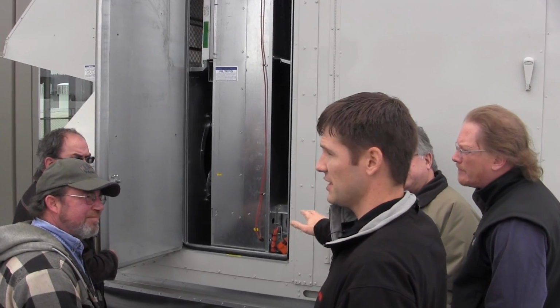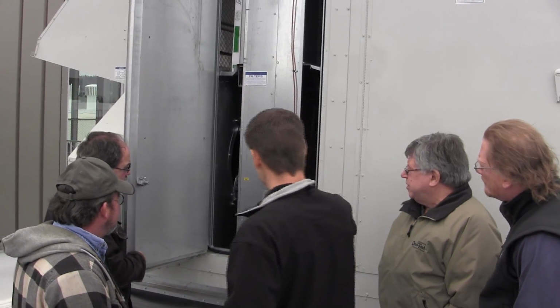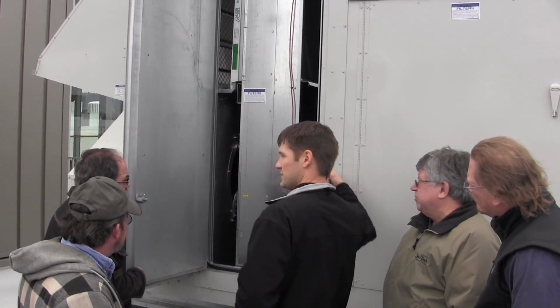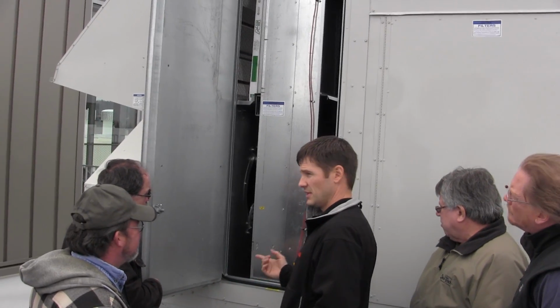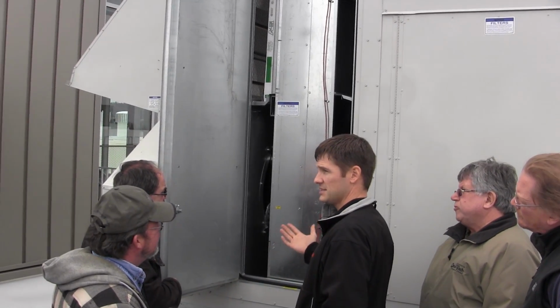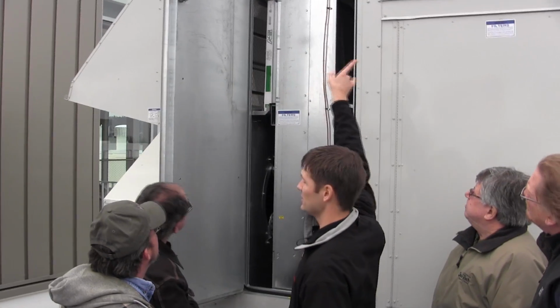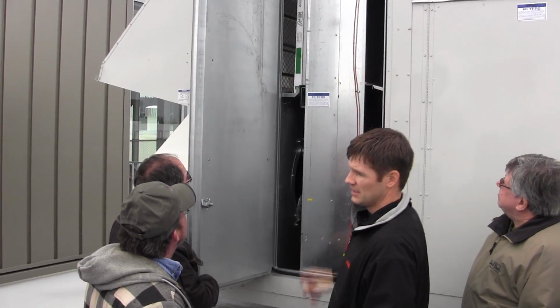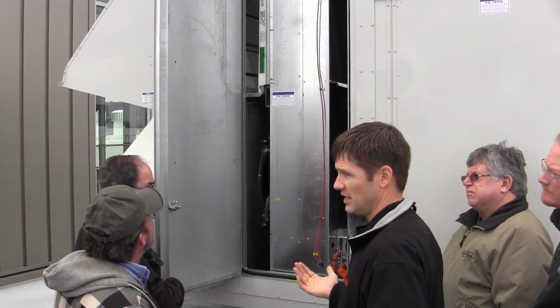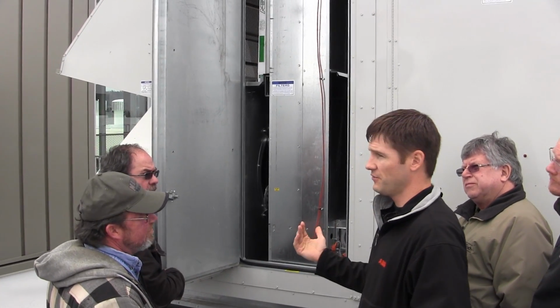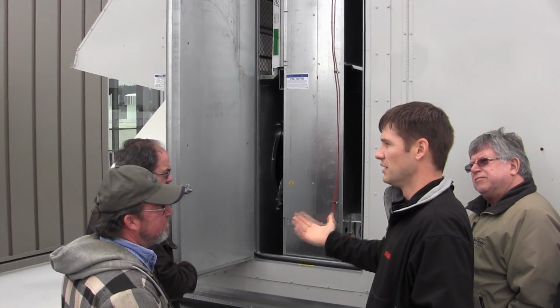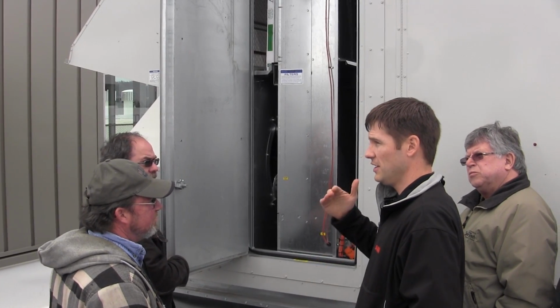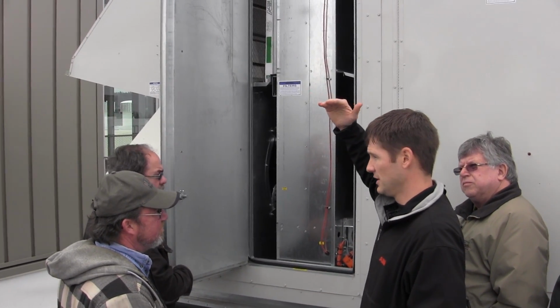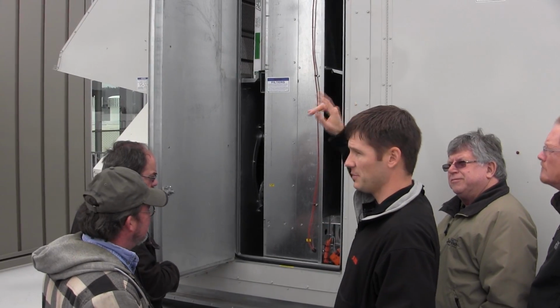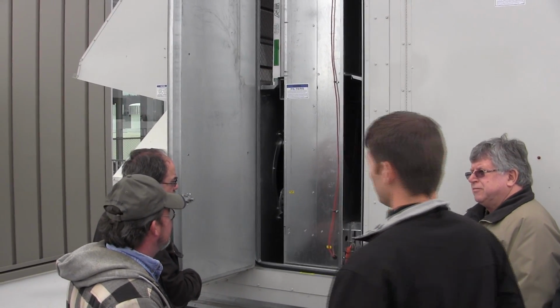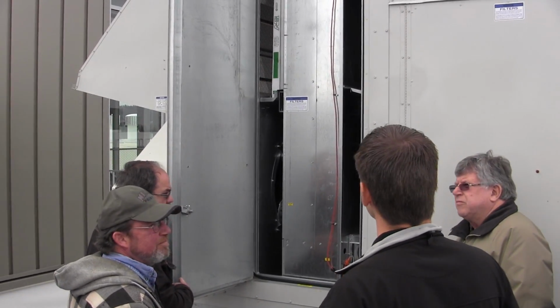But if you wanted to modulate temperature, for instance, this exhaust would allow some air to not go through the wheel. It would give you less pressure drop and less heat recovery. Same on the outside air side. You could bring fresh air in without heat recovery. So if you were trying to do economizers, for instance, and you wanted 55-degree air, the air was 45 outside, but your heat recovery is going to bring it all the way up to 65, but you want 55. You could open those up and get less heat recovery. And that currently is not part of the sequence, I don't believe. It might be.